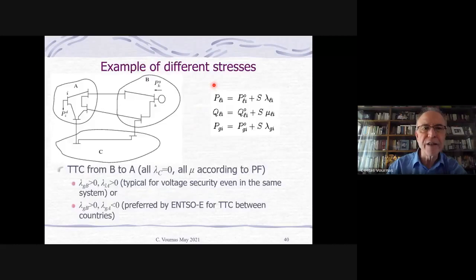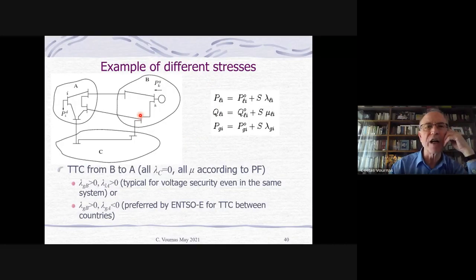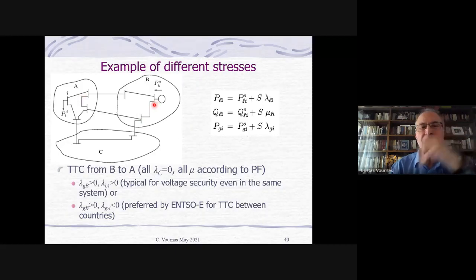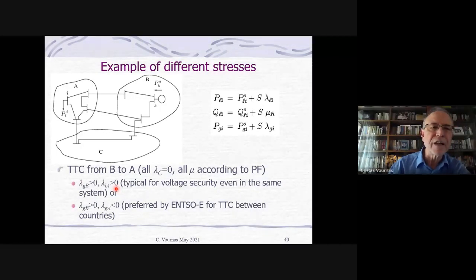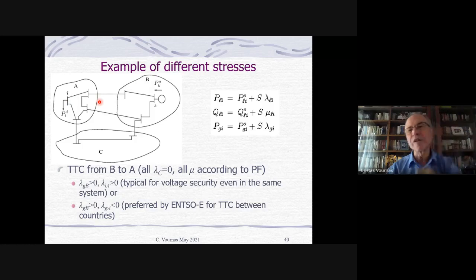You can see in this case that I can find the maximum power I can transfer from area A to area B. For instance, if I increase the load in area B and also in area C, I get another limit. And if I increase the generation at area B and at area A, I get also another limit. So assume I increase the generation at area B and increase the load in area A - I get the maximum power transfer from area B to area A. So this is a multi-dimensional problem, but I can see it in a single dimension, which is the direction of the stress.